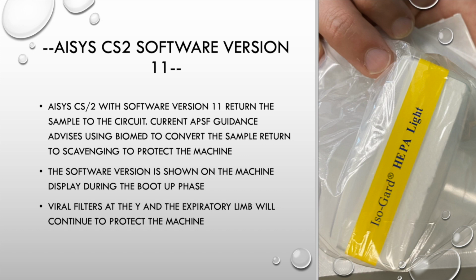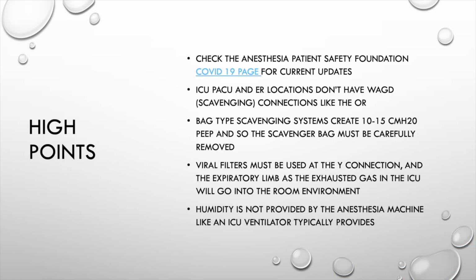As I said before, software version 11 returns the sample line to the circuit. The current APSF guidance advises using Biomed to convert the sample return to scavenging instead of back to the machine. That will protect the machine in all scenarios. If you're ever curious about what software version it is, the version is shown when you boot up the machine on the screen. And again, the advice in the APSF guidance resource is to place viral filters at the Y and the expiratory limb.